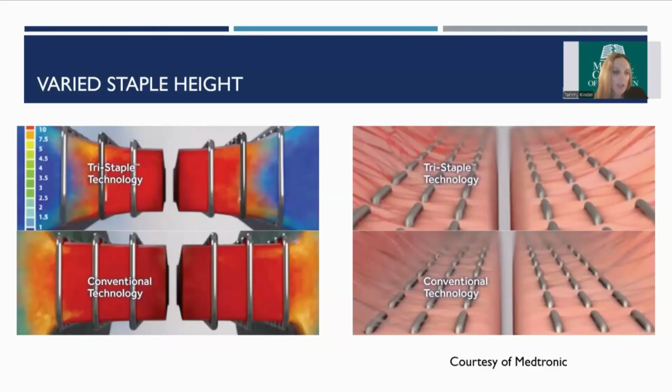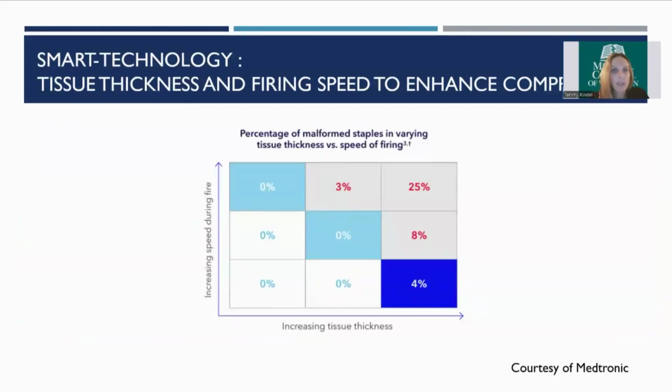The manufacturer does describe the graduated compression profile and varied height of staples also allowing greater tissue perfusion into the staple line. And it is believed that having perfusion at the end of the staple line is important for ultimate healing.